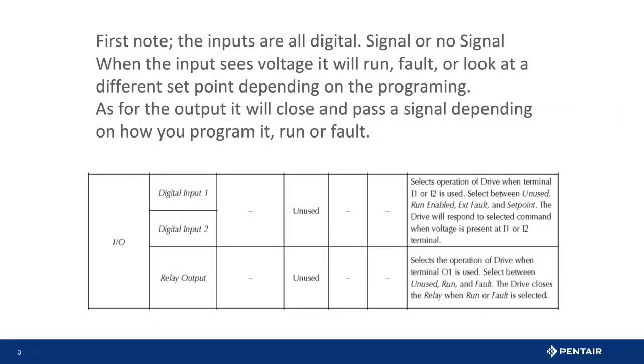Diving deeper into the input and output, it is important to understand all three are digital, meaning there is a signal or there is not a signal. On or off. Is there an analog input, and what does analog mean? Well, to answer the first question, yes, the transducer input plugged into the AI plus and minus connections. To answer the second question, what is an analog signal? It is a range. A good example again is the transducer that reads pressure from 0 to 100 pounds of pressure and anywhere in between.